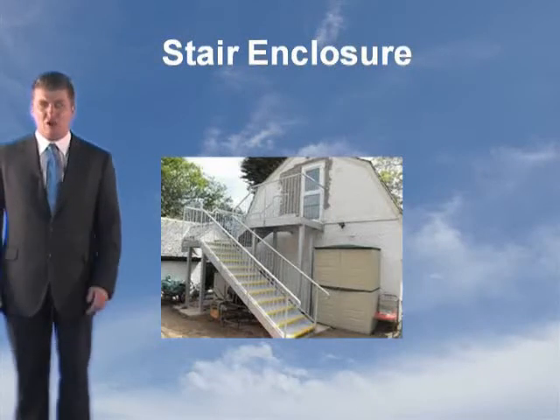What about the stair enclosure then? Now, the fire-resisting construction of escape stairs does offer protection to anyone using these stairs, and they are deemed to be a place of relative safety. If it's a protected staircase, the travel distance stops when they reach the stairway because it's deemed to be safe. In other words, now they're in there, they're safe. And this reinforces the importance of building occupiers keeping self-closing fire doors in the closed position. Because once they get in there, they're deemed to be safe. If the self-closer doesn't shut or there's no seal on there, you've lost your staircase. So make sure you protect your staircases with your fire doors for means of escape.